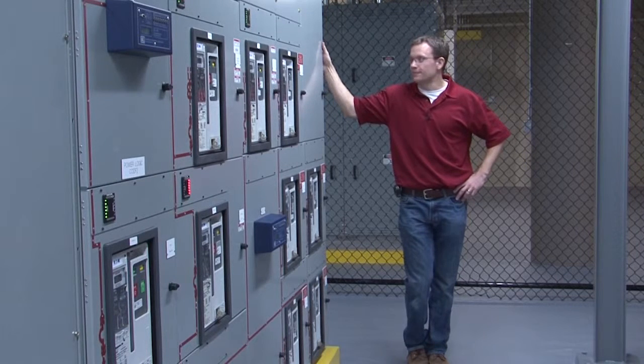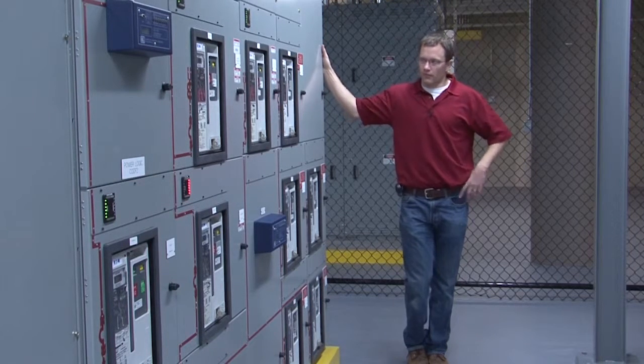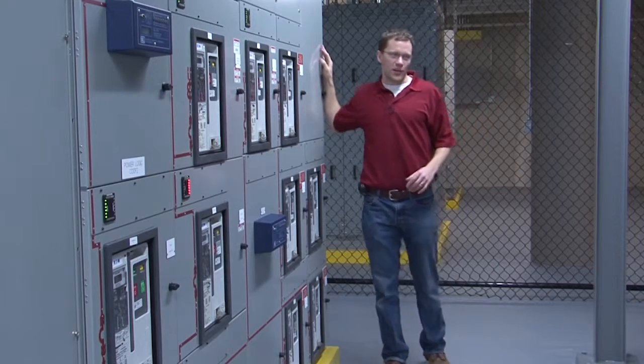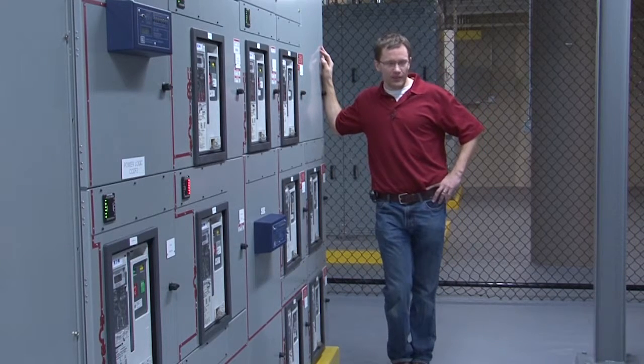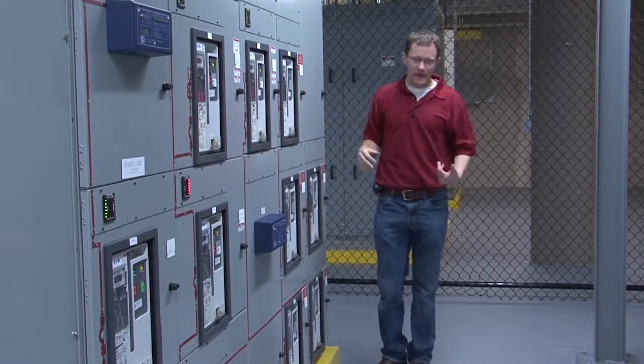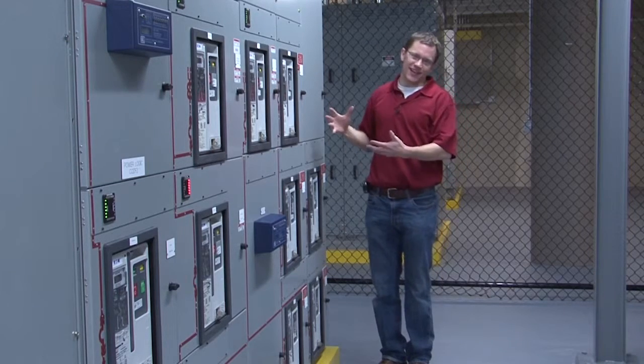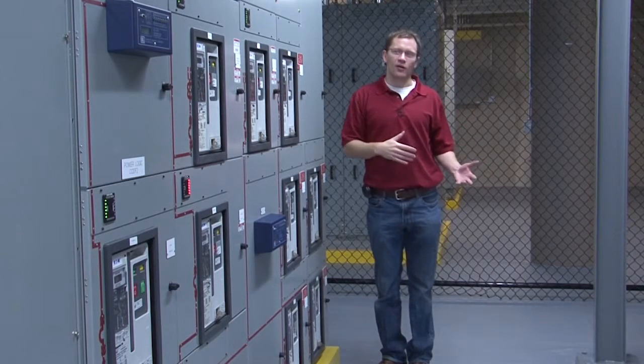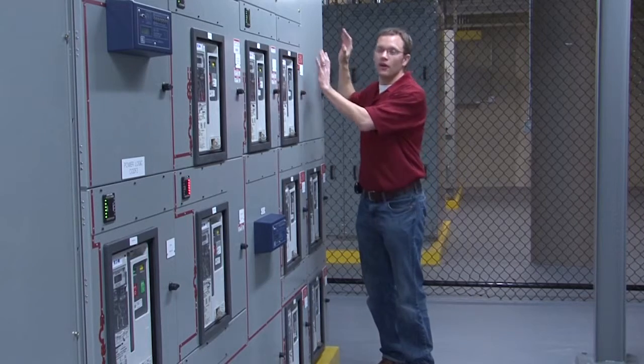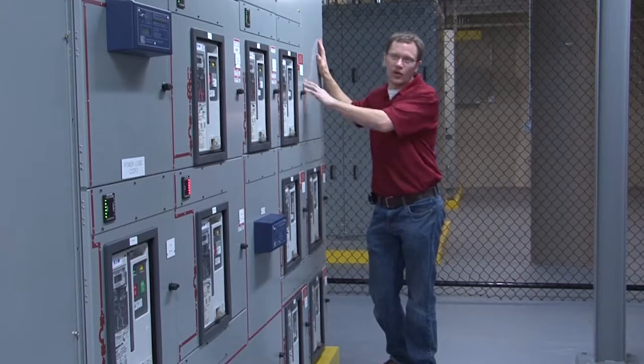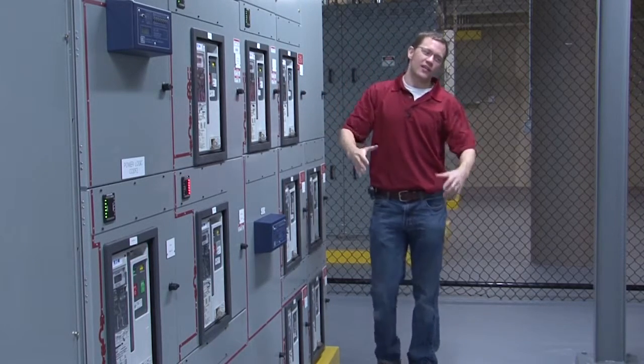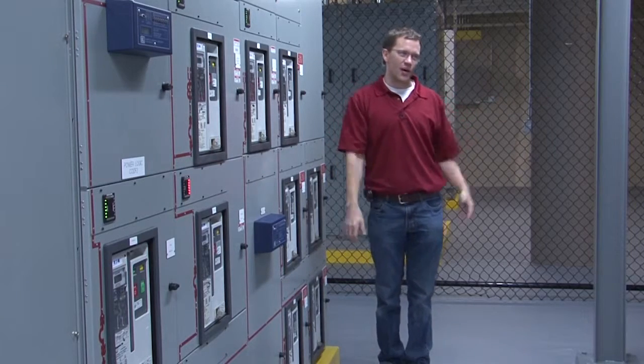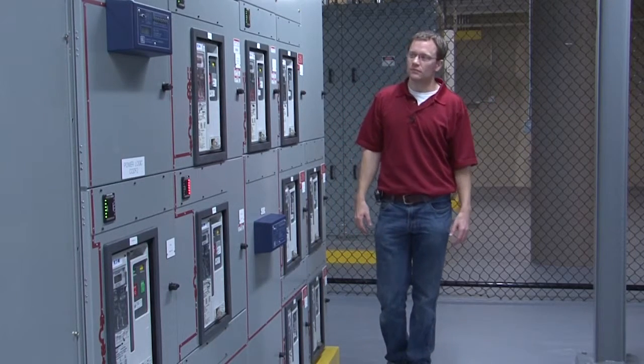All right, so now we've talked about the UPS input substation F2. That substation feeds the UPSs. The UPSs then in turn send output power to a COD board, in this case COD F2. So each UPS input substation has associated UPSs and an associated output board.